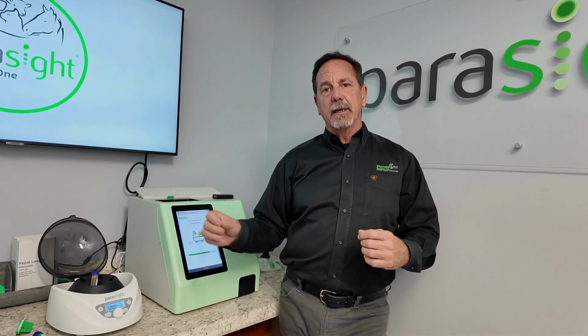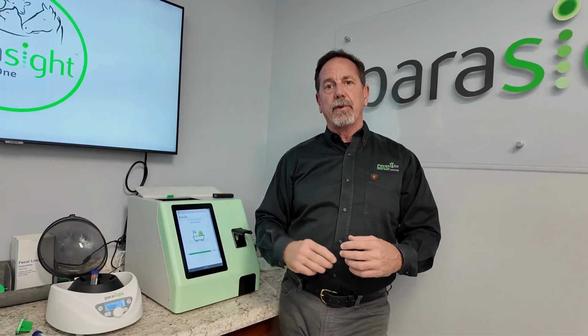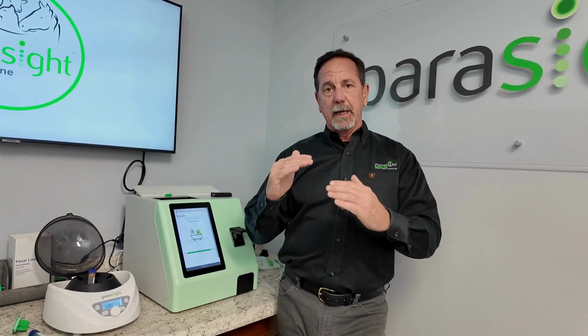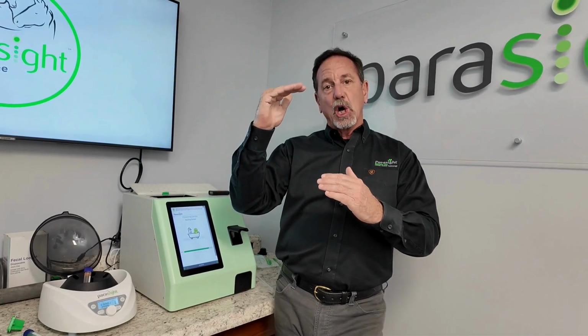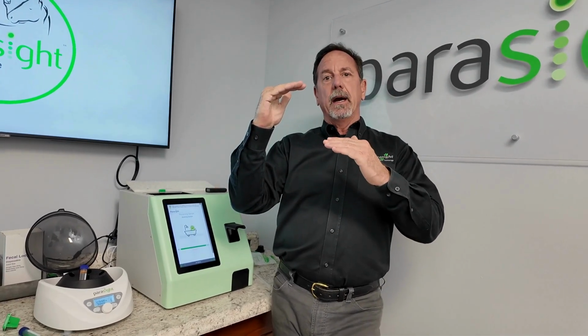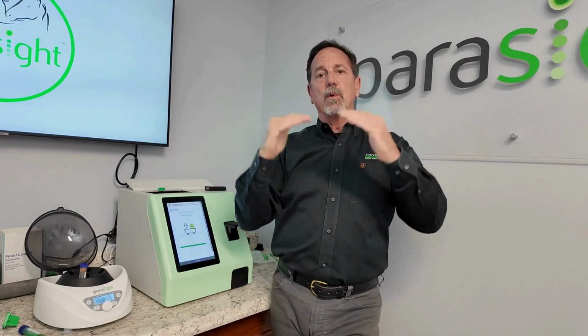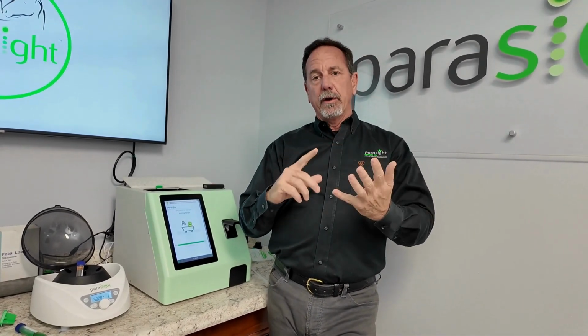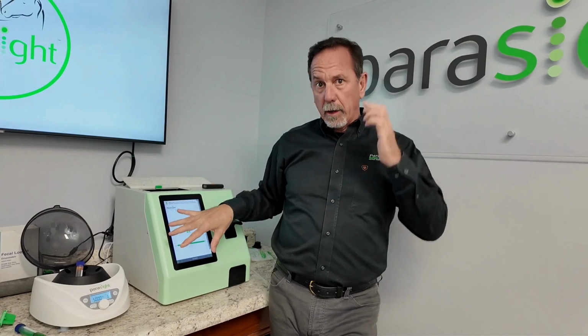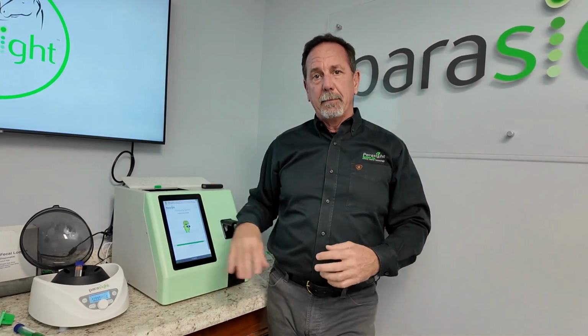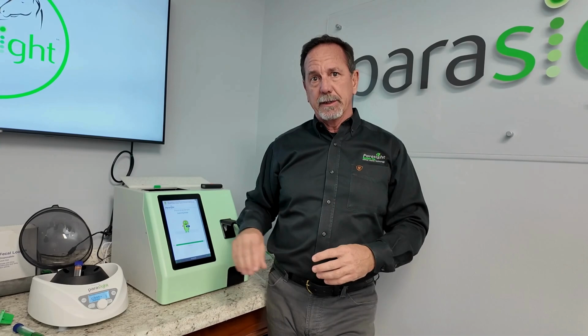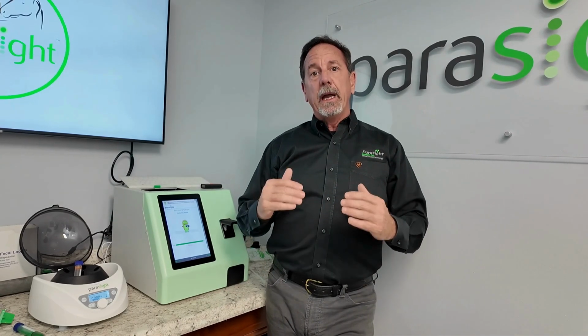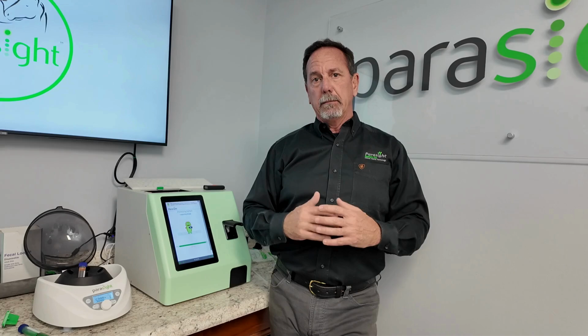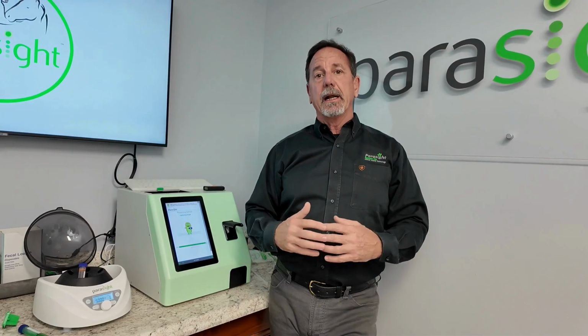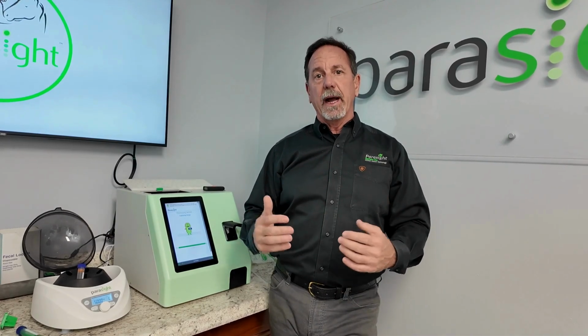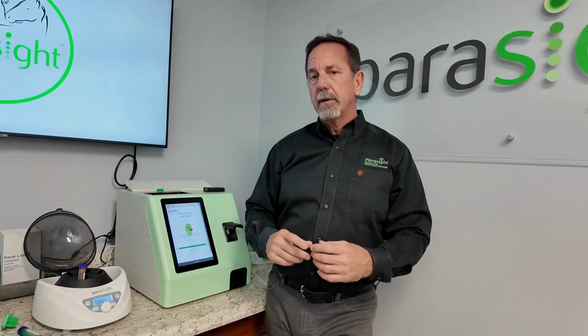that specimen and pouring it through or looking at it will not work, because lipids or fats along with the eggs will float to the top and they will clog either your slides or the sample specimen chamber in the case of using the Parasight system. We are the only system out there right now, technology-wise, that allows a way to work through that, and it's very simple to do.